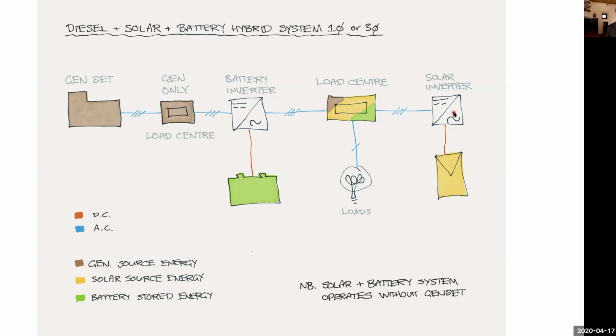So those two methods, frequency shift power control and direct management by a comms system, are required when you don't have somewhere to spill the surplus power. So really this arrangement I've drawn here is somewhat a proprietary solution, not a generic solution, though frequency shift is becoming very common because in Australia and New Zealand our inverter standard actually requires that mode to be available on grid tie inverters, that they have a frequency shift power control feature. So they will do it kind of anyway.